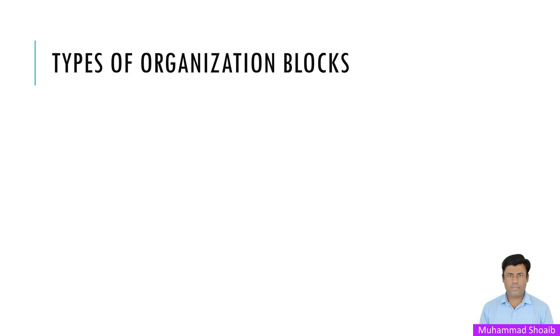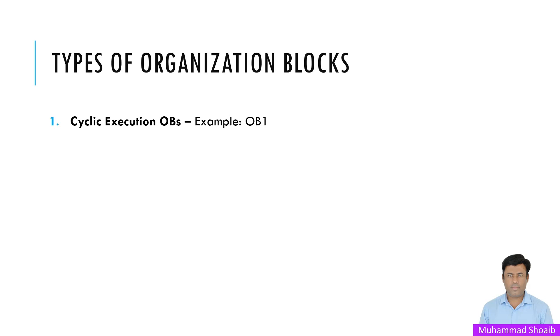Now let's go over the main types of OBs using the Simatic Manager. So first is the cyclic execution OBs, for example OB1. The most important OB is OB1, it runs continuously in a loop, processing your main logic. Everything you program here will execute every time the PLC completes a cycle. This makes OB1 essential for tasks like reading sensors or controlling motors.